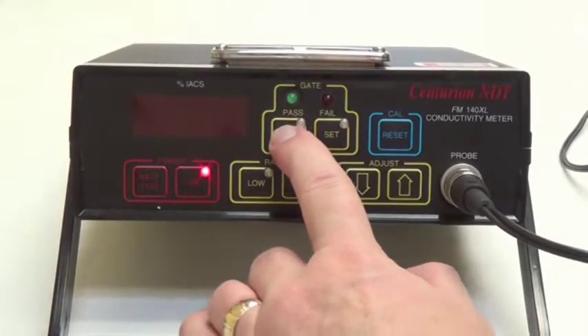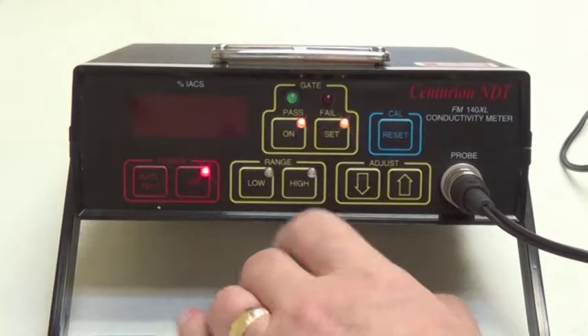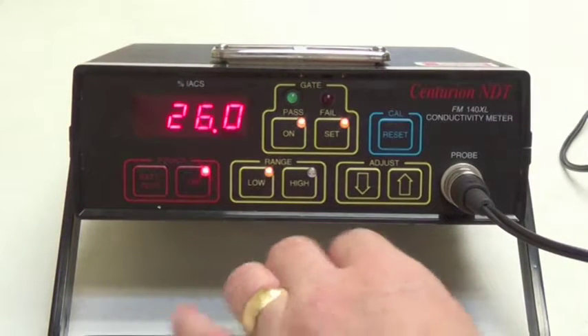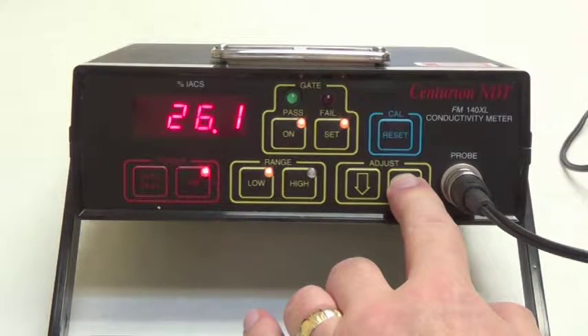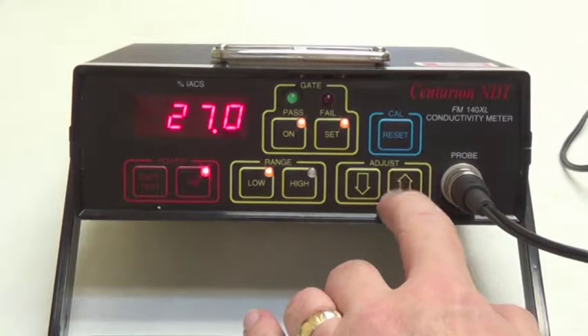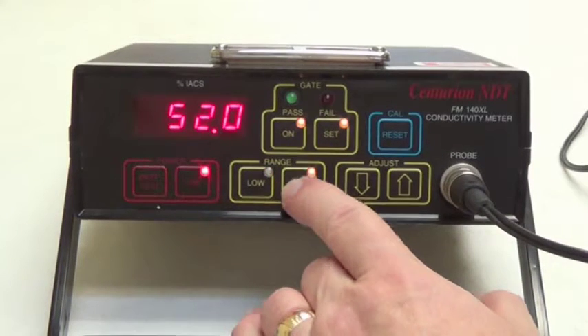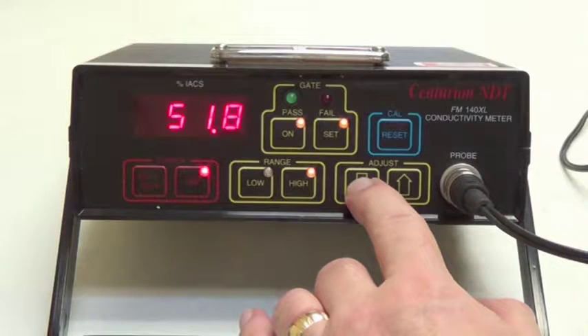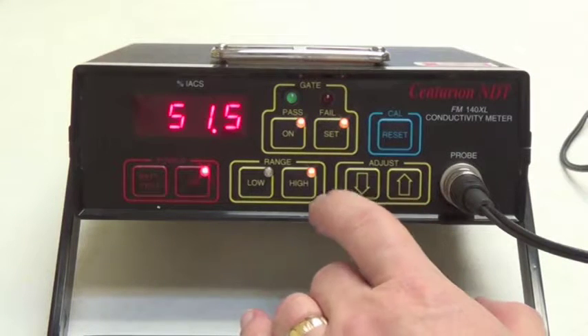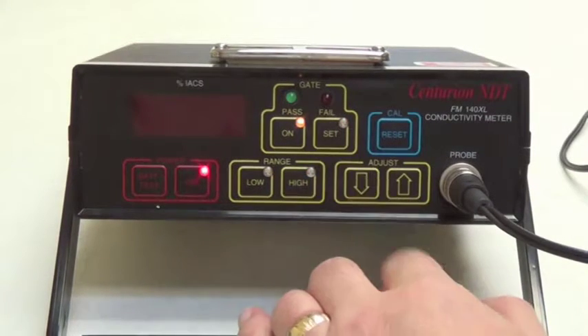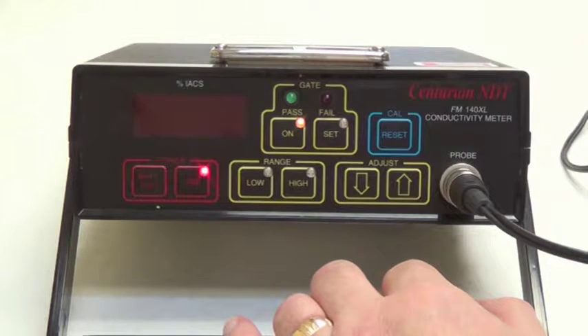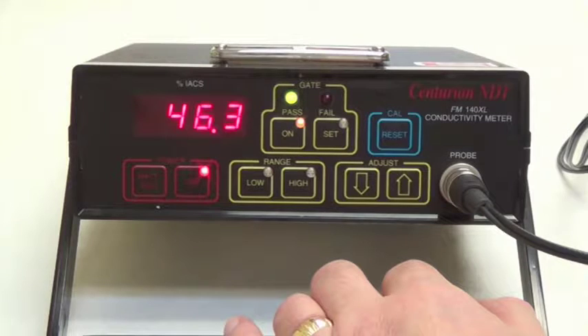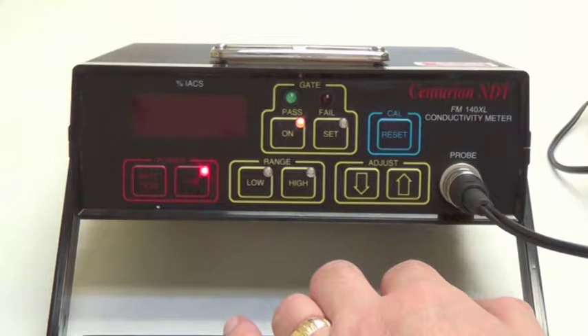To set the gate, press the on push button and then the set. To set the low limit, press the low push button. Use the up and down arrows to set the value of the lower limit. Pressing the high push button will enable you to set the upper limit. When finished, press the set push button. The on LED will remain lit. Now when the probe is placed on a sample within the range set, the green LED will light. Conversely, when the value is outside the range, the red LED will light.